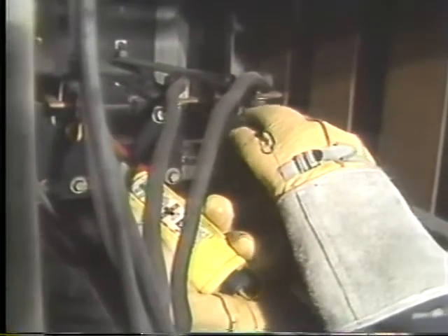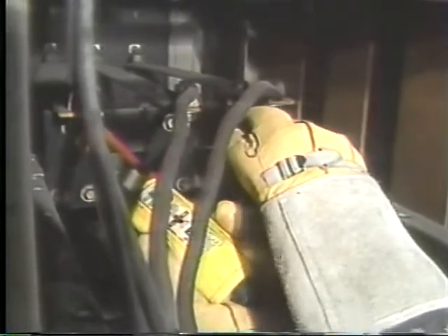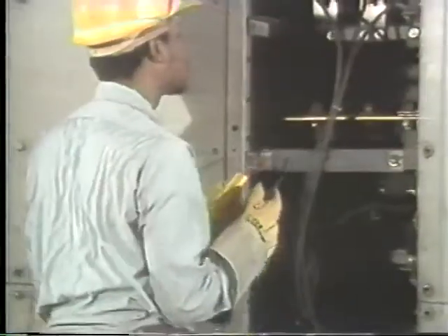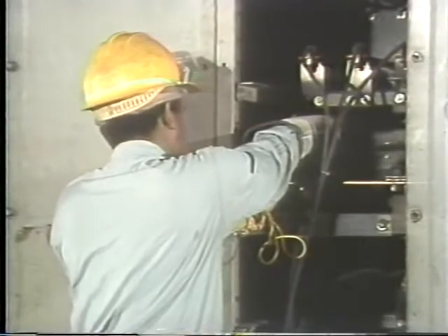Next, he checks the breaker load terminals where the temporary feed is attached. He checks line to ground and then across all three phases. Now he's sure that the load terminals are dead. That is, if the detector is still working. To make sure, he checks the main bus above the terminals. It registers hot, so he knows that the detector is working. And he knows that even though the main bus is hot, the breaker load terminals are de-energized.